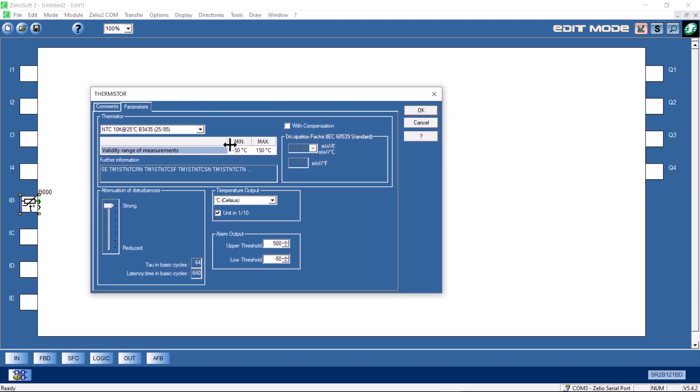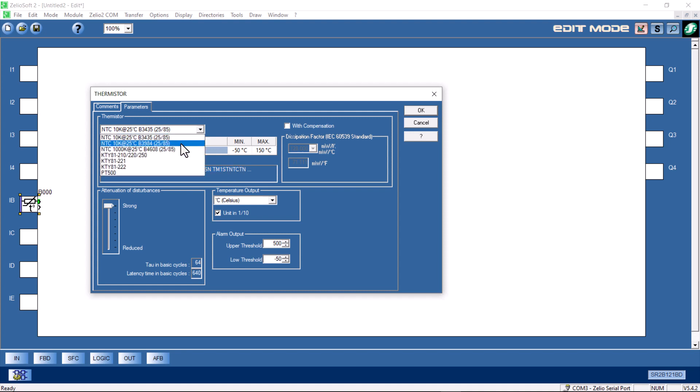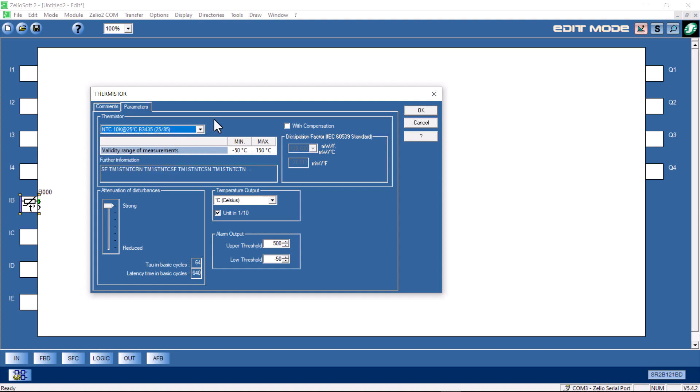I'll double click on it and have a look at the parameters. The default value is the parameters listed for the NTC 10K at 25 degrees C here. It refers to part numbers down below. Those are those Schneider part numbers. Under further information, those are those Schneider part numbers that I showed you in the catalog. There are numerous other options to choose from. But in this case, we will go with that commercially available unit from Schneider. So we've selected the sensor.